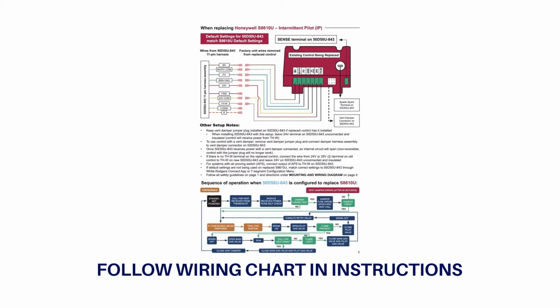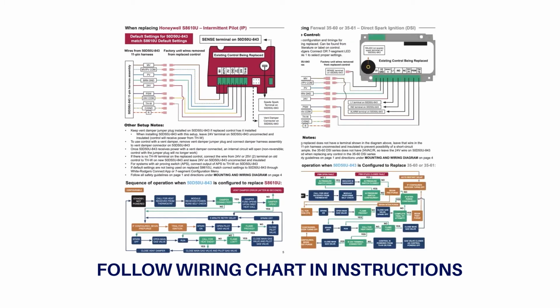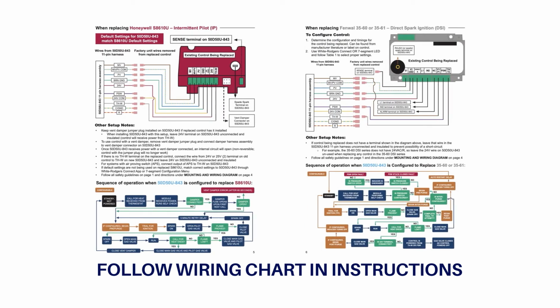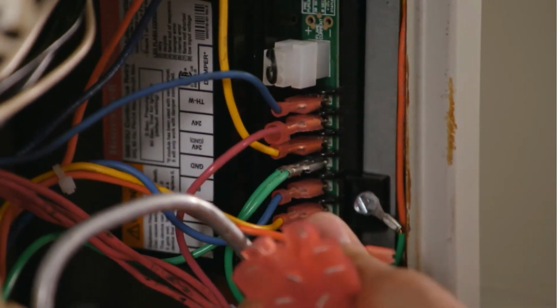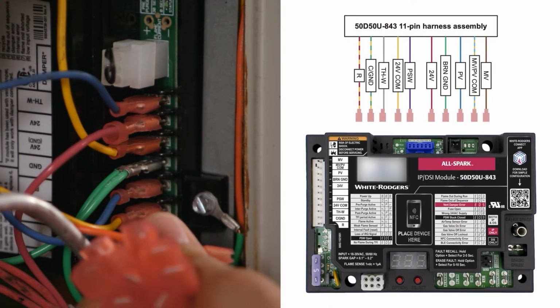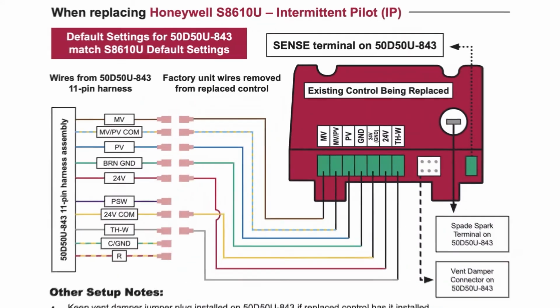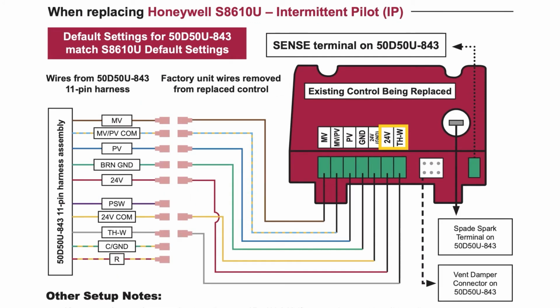The installation instructions come with a diagram showing wiring connections for both an intermittent pilot system and a direct spark system. For this application, the intermittent pilot diagram will be used. Individually disconnect and transfer each wire from the existing control and connect it to the appropriate quick connect terminal on the 50D50U-843 11-pin harness or dedicated spade terminal on the printed circuit board. Note in the instructions when a module does not use both the 24-volt and THW terminals, install the 24-volt wire on the harness wire labeled THW.